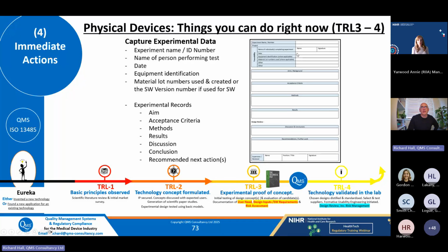You need to record the equipment that was used and the material lots that were used. That will cover you for the calibration and the material traceability. There might be other things you create, you document, and then down here, these are explained down here. So the aims, the acceptance criteria, methods, results, discussion, conclusion, and recommendations for next work. Just really basic stuff that if you leave it to people to do on their own, they quite often miss some of these steps out. So create a form and make sure it's used religiously within your organization. The thing that gets missed all the time is acceptance criteria. If you say, well, this needs to be 95% accurate before it's a thing, and you get to 94%, you might go, it's probably good enough.